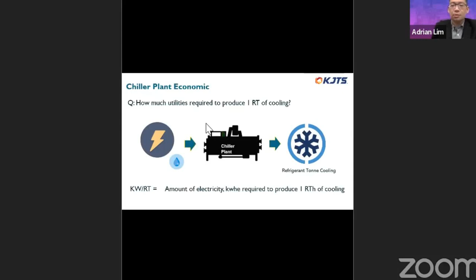For the benefit of the audience who aren't familiar with the DCS industry, the key takeaway pertaining to the economics of the DCS is the cost of production, or COP. In a nutshell, it's fundamental to know how much utilities are required to produce one refrigerant ton of cooling energy. Once this is measurable, only then can we attempt to improve it. Ideally, you'd want to pay as little as possible to gain as much cooling energy.